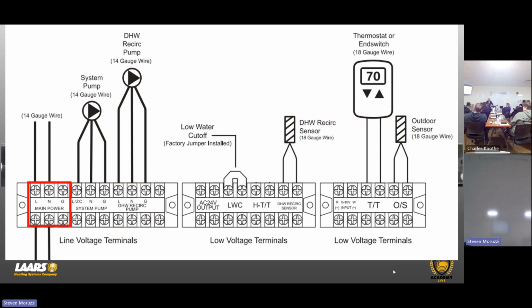All right, back to the terminal strip. So we've got main power. Now, depending on how we're going to control this, are we doing zone pumping or zone valves? Okay. So we're going to have a system pump and domestic recirculation pump, maybe. Okay. And I'll get into how we actually wire up the system pumps in a minute.